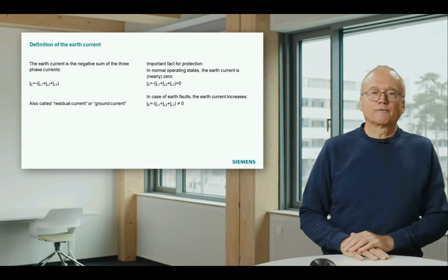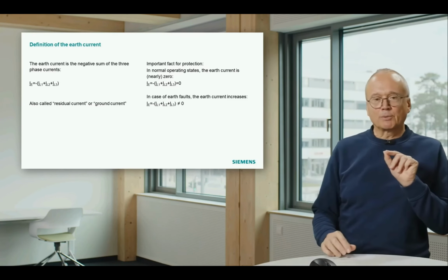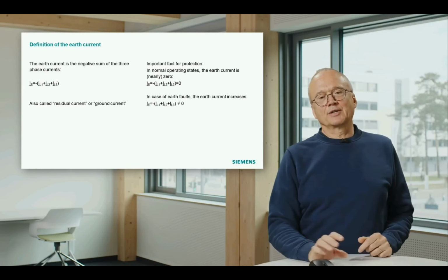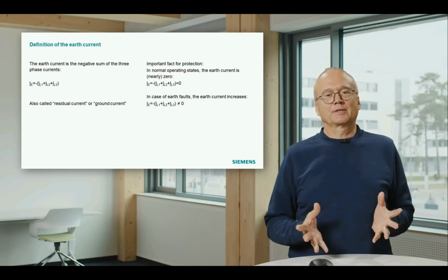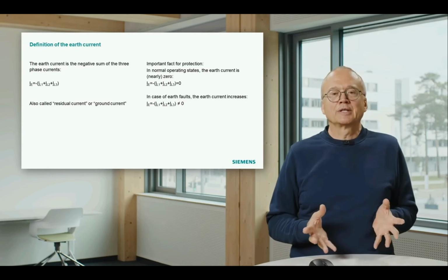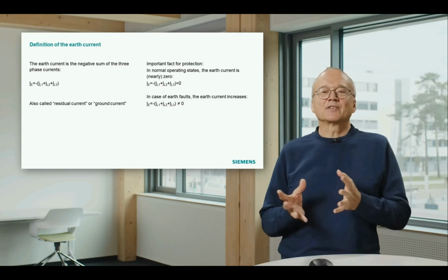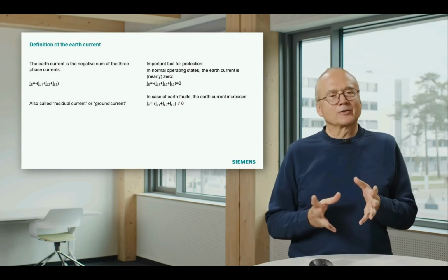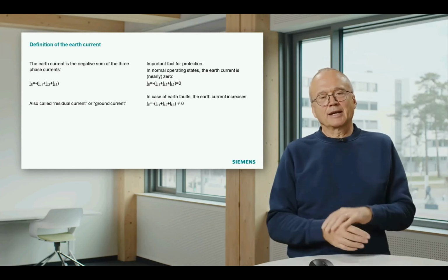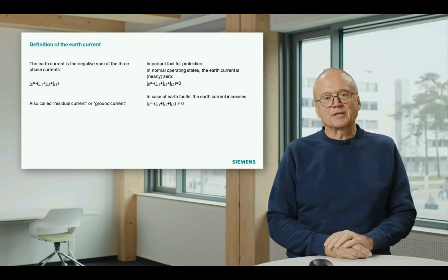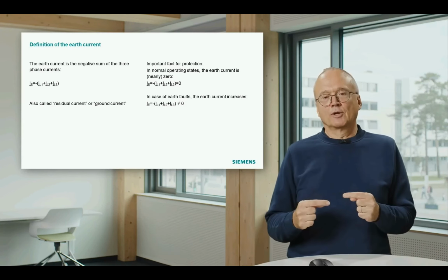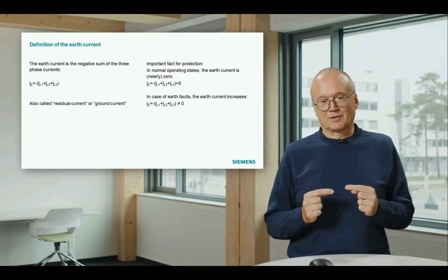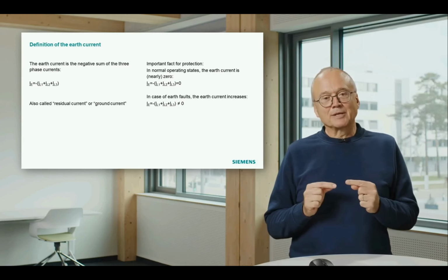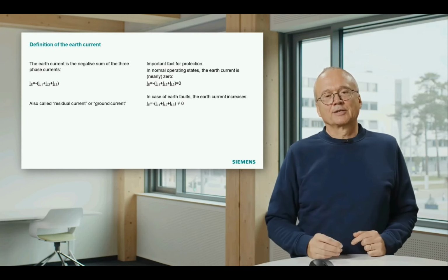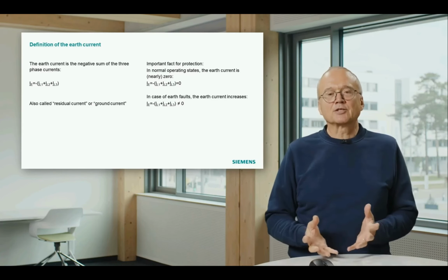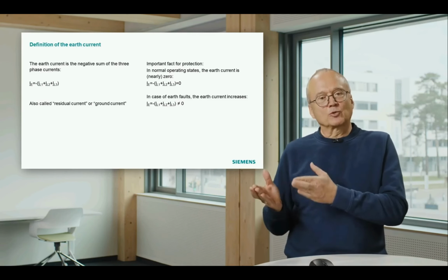But what is now the important fact for protection? The interesting thing for protection is that this earth current is in normal operating states, that means in operating states where we have no fault, nearly zero. It's not exactly zero because we have some asymmetries in the system, but it's nearly zero. And in case of an earth fault, this earth current increases. And that means we can use the earth current as a very sensitive criterion to detect phase to ground faults.